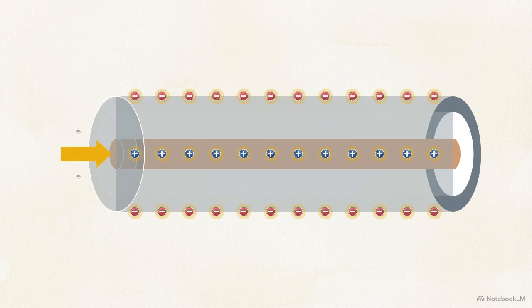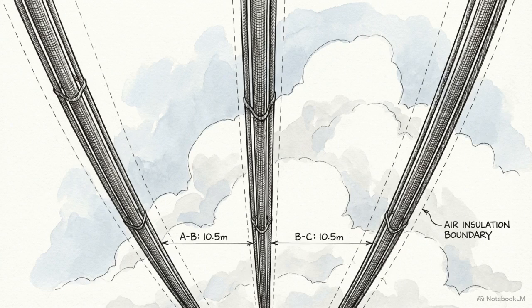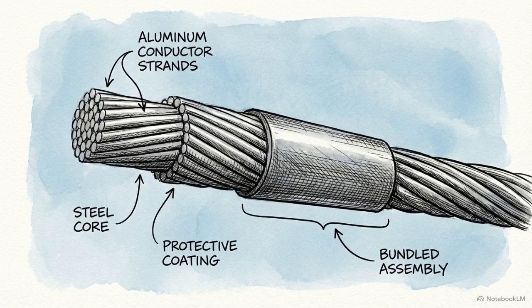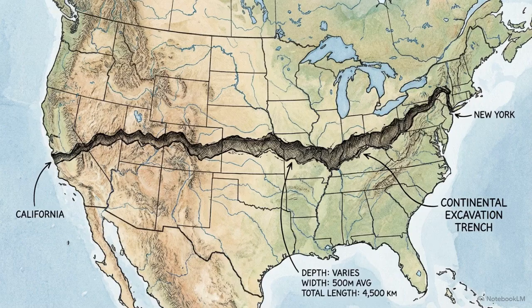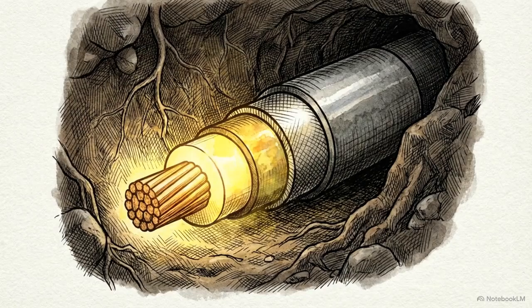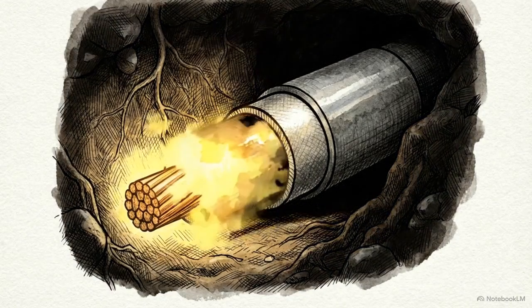As alternating current pulses through the line, it constantly charges and discharges this capacitor. This generates a parasitic charging current. The longer the underground cable gets, the more reactive power it absorbs, eventually choking off the actual useful electricity you are trying to deliver. Overhead lines avoid this trap. The vast spacing between the wires in the open air means their capacitance is incredibly low, leaving the full capacity of the wire available for useful power. If we tried to bury a standard alternating current line to cross a continent, the charging current would consume 100% of the power capacity before it ever reached the next state.